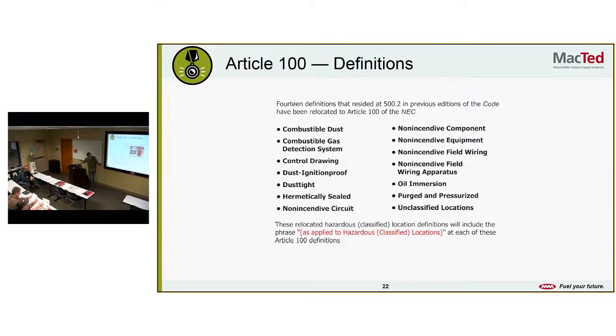Article 100, definitions. 14 definitions that resided at 500.2 in previous editions of the code have been relocated to Article 100. We talked about this in the last part where they've consolidated a lot of these articles. They've relocated those ones you see there. These relocated definitions will include the phrase as applied to hazardous classified locations at each of these Article 100 definitions. So if you go looking for those around 500.2, they're now in Article 100.